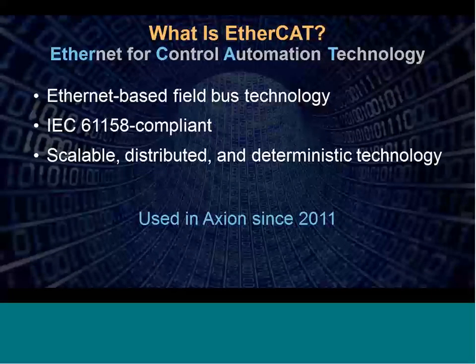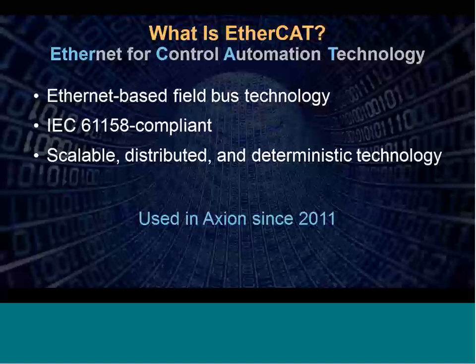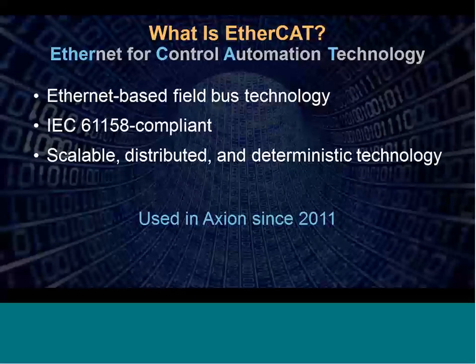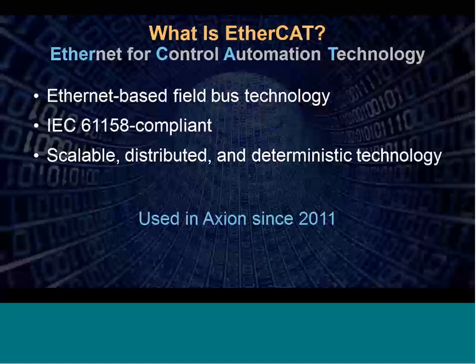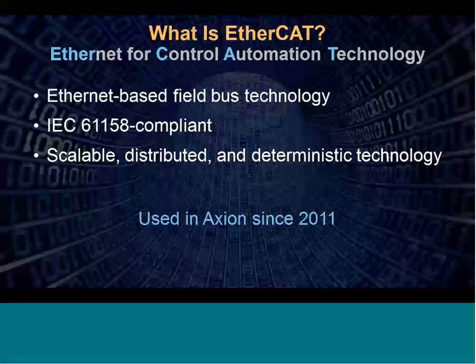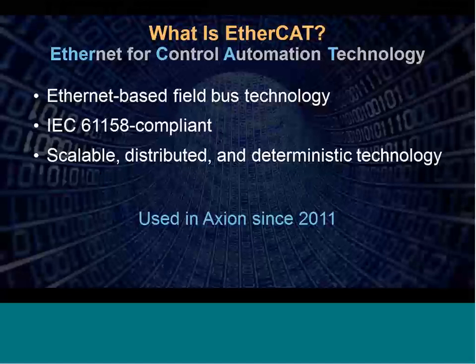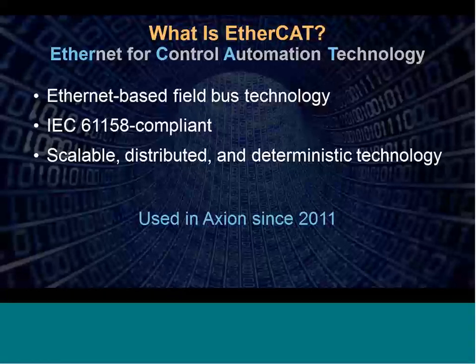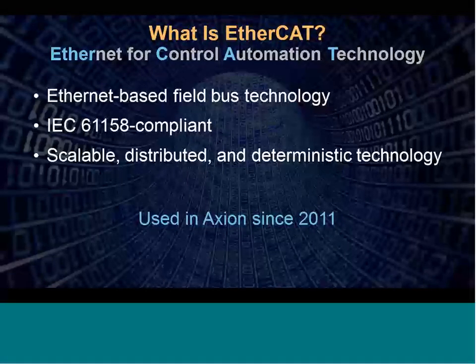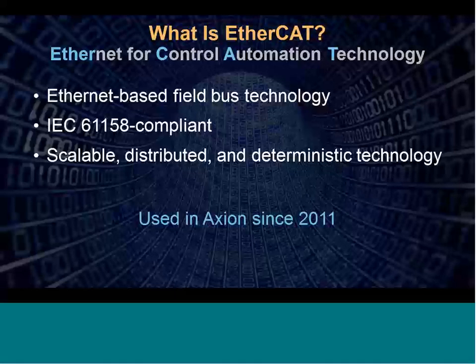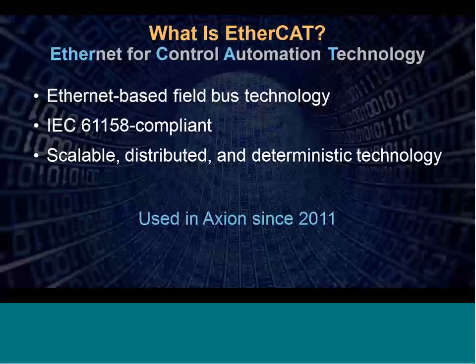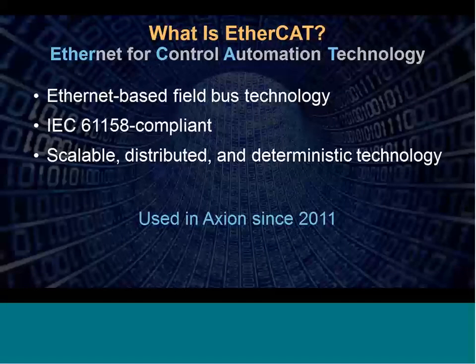So what is EtherCAT exactly? It's Ethernet-based field bus technology, meaning the physical connections are the same as an Ethernet connection. It's a multi-mode fiber connection, but if we were to put it into an Ethernet switch, it would not recognize it as Ethernet. It's IEC 61158, originally built for industrial I/O expansion, so it's a very scalable and distributed application, but most importantly, from a protection perspective, it is very deterministic.